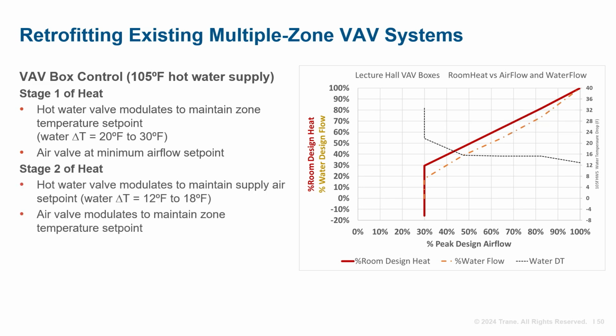If the heating load increases in stage 2 of the heating, the hot water valve modulates to maintain the supply air temperature at a set point of 85 degrees, for example, while the air valve opens further, modulating to maintain zone temperature at set point. During stage 2, the water delta T is 12 to 18 degrees.